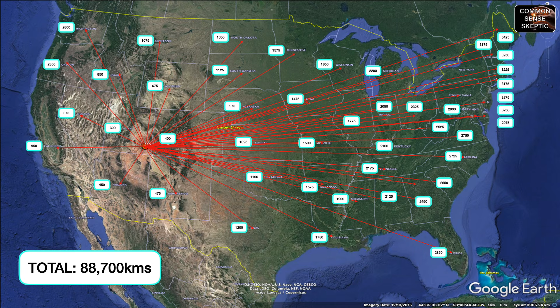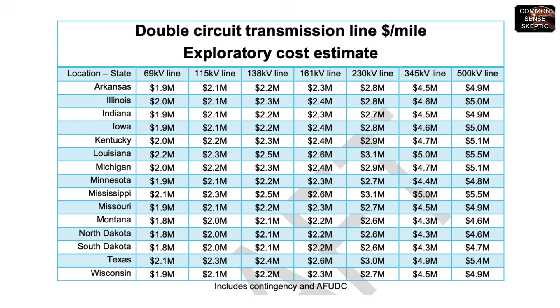We took this map and figured out how many kilometers of each line we would require if they could be run as a straight shot between Utah and each state's central point. It turns out we're looking at around 88,700 kilometers, or 55,440 miles, of lines. At an average of $5.1 million per mile, a set of 3 double-circuit 500 kV lines would run around $865 billion. At roughly $3 million per mile for the 230 kV double circuits, that's another $500 billion. Added up, that's $1.365 trillion on this tally.